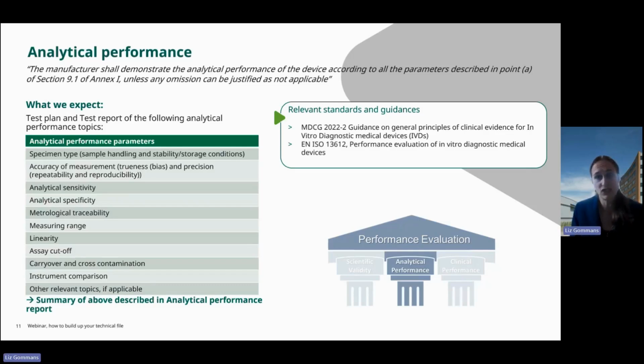In the report we need to see sufficient detail to allow us to make a proper judgment if the test has been properly done, and if the results are acceptable or not, potential outliers, all these kinds of things we expect to see in the test report.